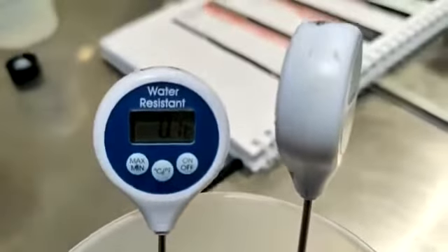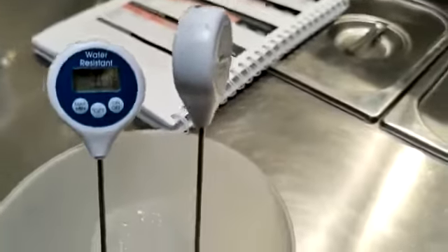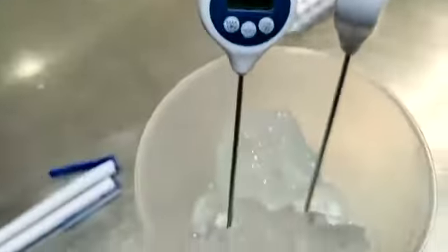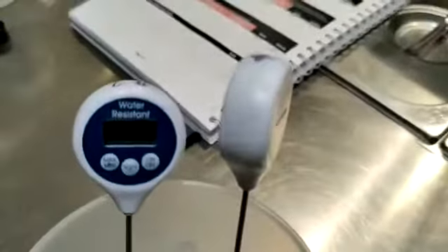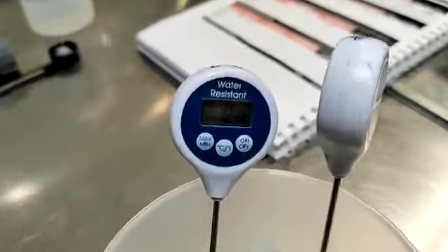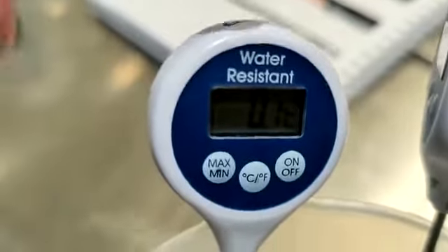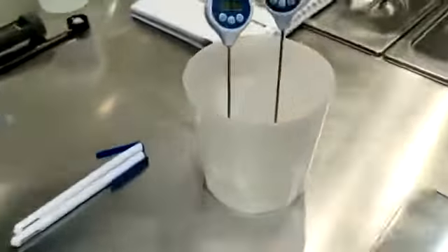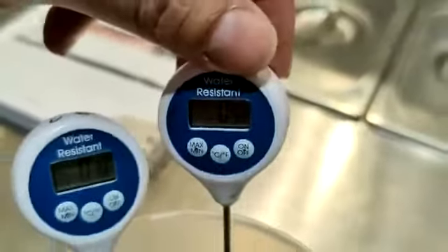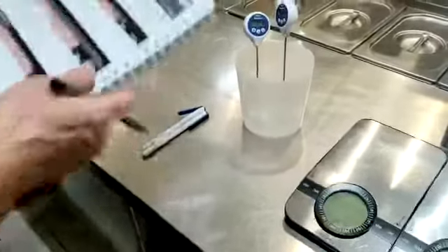We do probe calibration. You know, the ice and the water, and then we dip the probe inside the ice and the water, and the temperature has to be between 0 and 0.5 degrees Celsius. So here on the screen it is 0.1, which is correct, and here 0.5 is correct. Then we write it down here. Temperature probe calibration, probe number 1, 0.5, and number 2, 0.1. We don't have probe number 3 and number 4. Corrective action not applicable, and then the date for today, and then initial. So we are done with the probe calibration.